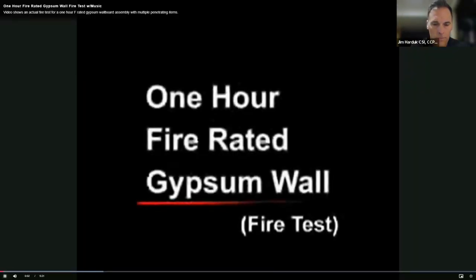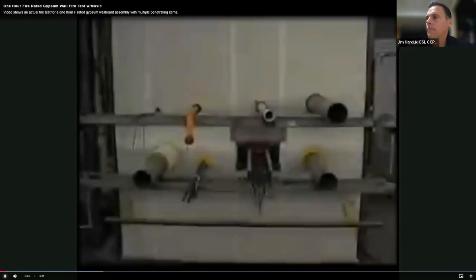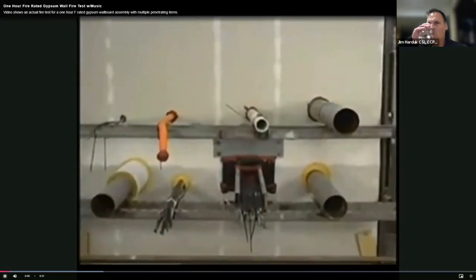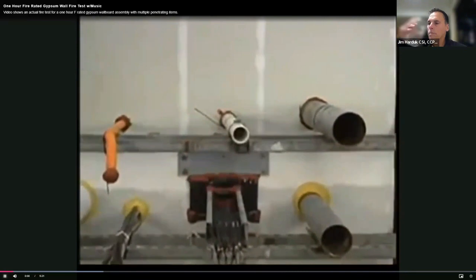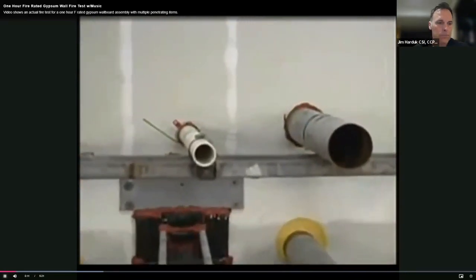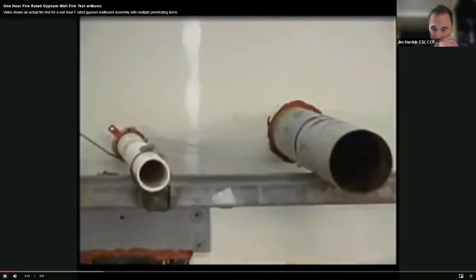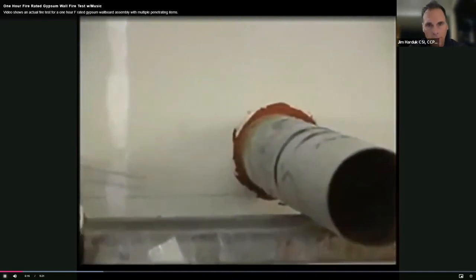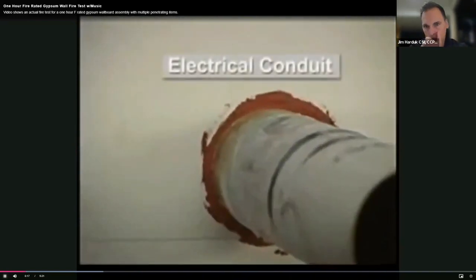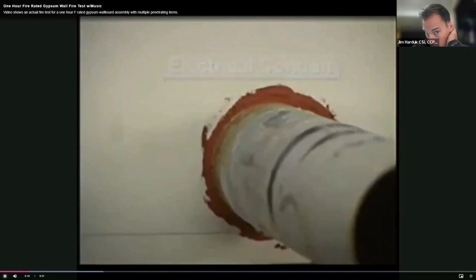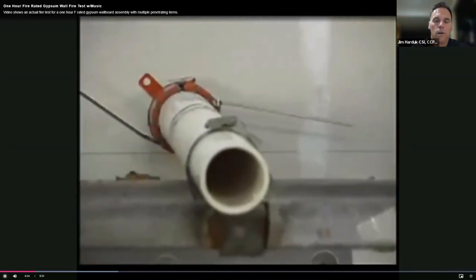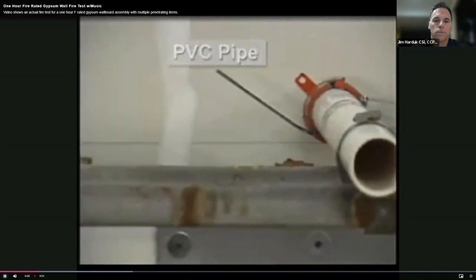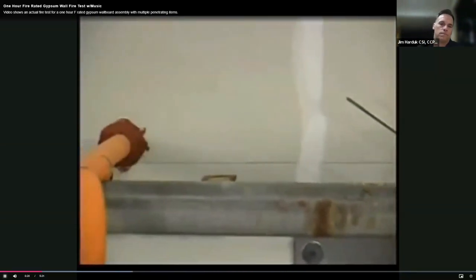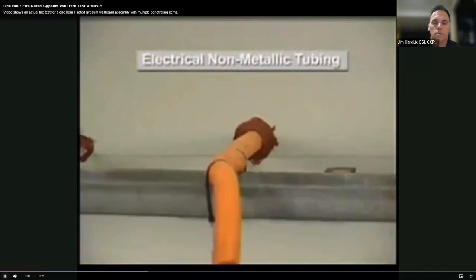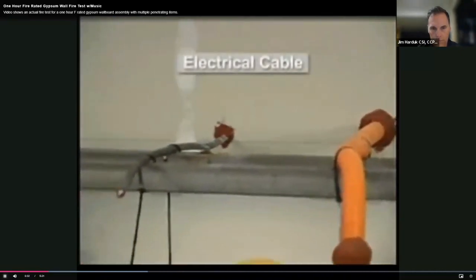1 hour gypsum wall fire test. The following video is an example of an ASTM E814 fire test. The fire test will follow the ASTM E119 time temperature curve. The wall can be constructed from steel or wood studs with the proper number of 5/8" Type X gypsum board layers on both sides of the assembly.